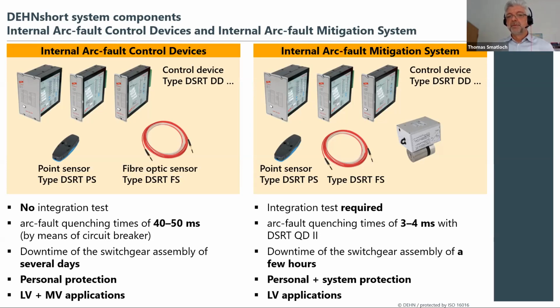So this is drastically reducing the quenching time to 3 to 4 milliseconds with this short circuiting element, what you can see here. In this case, the controller is not triggering the breaker in the equipment. It is triggering an active element, creating a bolted short circuit in the equipment. And after such an event, you have a downtime of such an assembly of a few hours. So in this case, you have to exchange this short circuiting instrument, and then you can run the equipment again. And in this case, we have personal and system protection. This is available for low voltage applications.